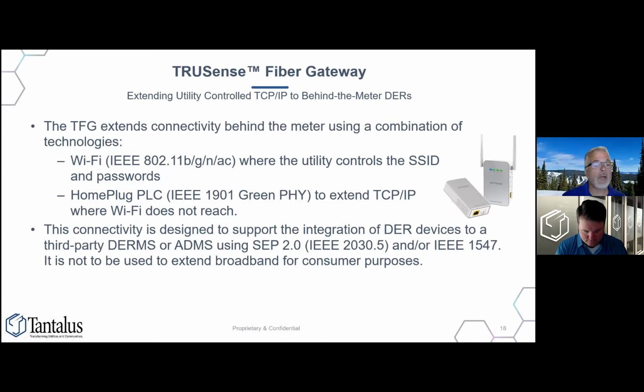This is an important point: the connectivity we're proposing is designed to support integration of DER devices to a third-party DERMS or ADMS using a number of different protocols. We're protocol agnostic, because there are a lot of competing protocols out there as people make land grabs. You've got Smart Energy Profile 2.0, now IEEE 2030.5, very popular in California, and also IEEE 1547. The good news is they both run over TCP/IP, and there are DERMS and ADMS systems that are bilingual, so they can speak both languages.